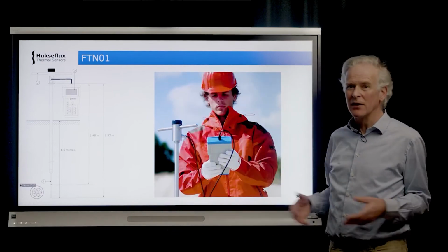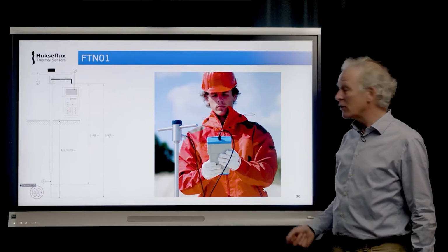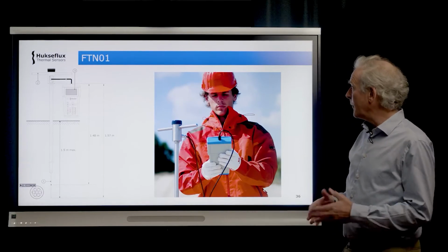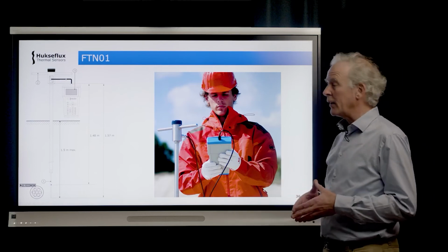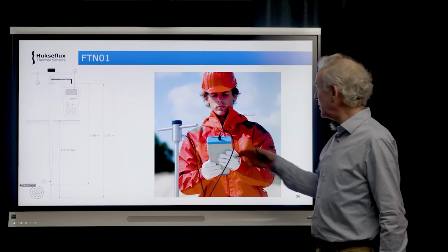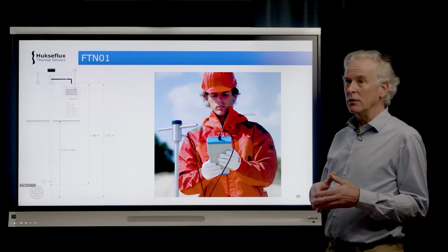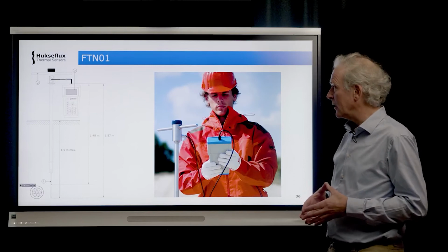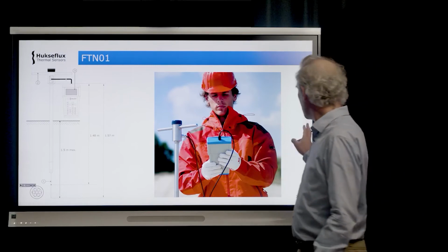Then you wait a bit until you reach thermal equilibrium, and then you start the measurement. A typical measurement duration is about 5 minutes for this needle type. Of course, depending on the situation, you first have to wait until there's stability. That might take longer than the actual measurement.